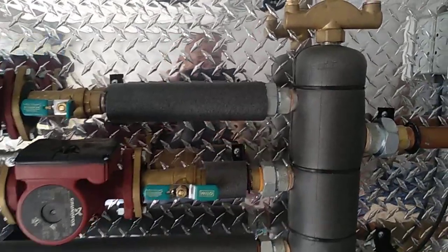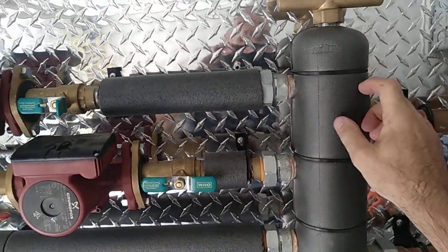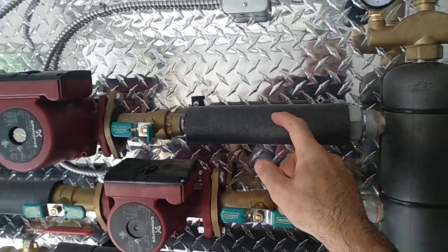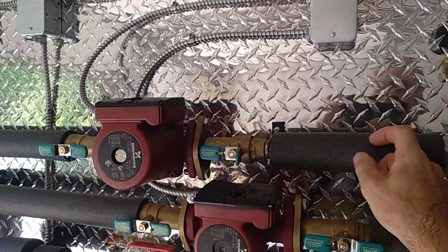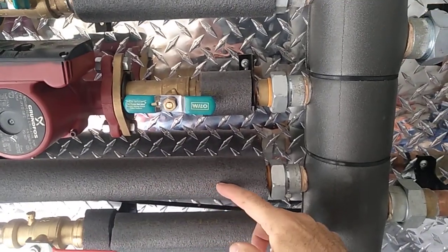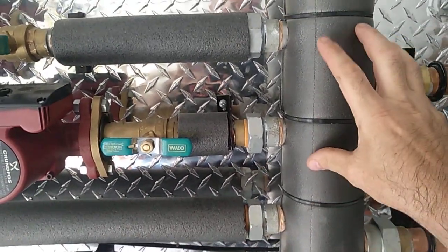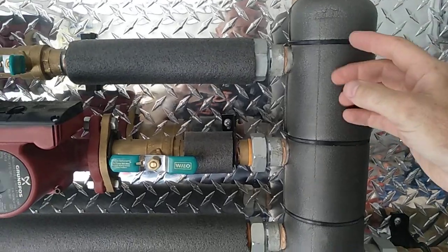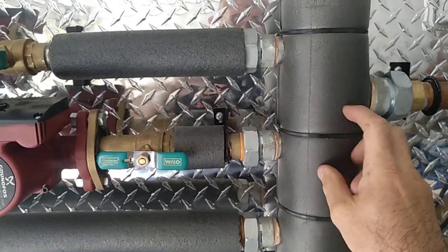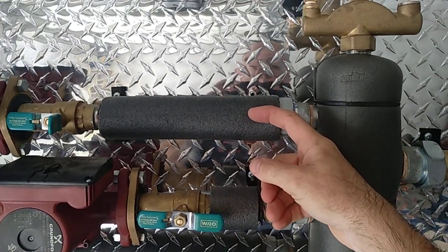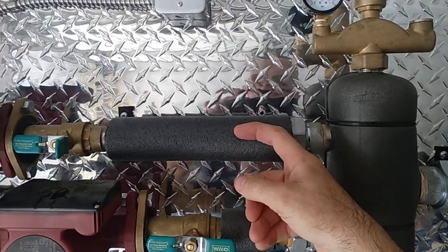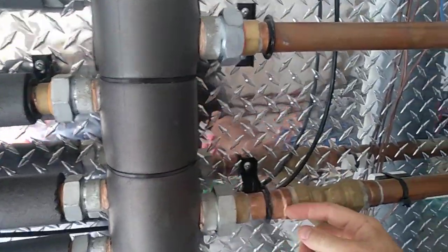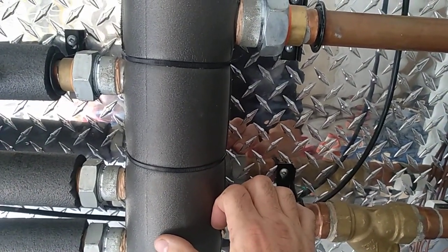So what this hydraulic separator does is that it not only allows the hot liquid to go out to the pump, as the cold return is coming back, it mixes together a little bit with the outgoing hot water. So let's say it's 160 degrees, coming back 10 degrees, it gets a little bit circulated, so immediately it's like 100 degrees going out, not 160 degrees or 70 degrees water going out. And also going back to the boiler is not minus 10 degrees, but it's also about 60, 50 Fahrenheit liquid going back into the boiler.